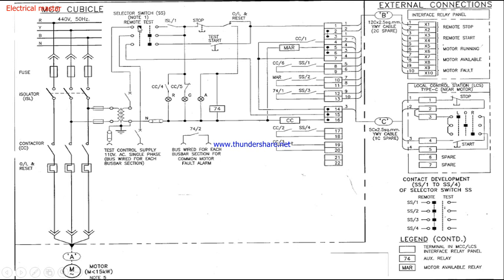For motor fault: the selector switch in remote position means SS3 is closed, and relay 74 — the auxiliary relay — when activated, its NO is used for alarm and also sends a signal for motor fault. From the NO that closes, cable number 10 is taken out and connected to terminal number 10 in the external interface panel, so the operator understands that particular motor has tripped or is faulted. This is the concept of the schematic diagram of a DOL starter, used mostly for motors up to 15 kilowatt or less in industry.